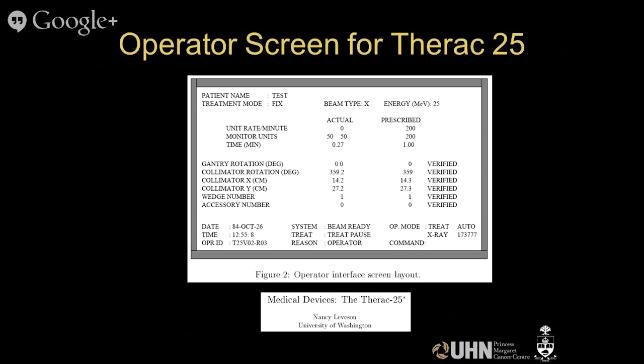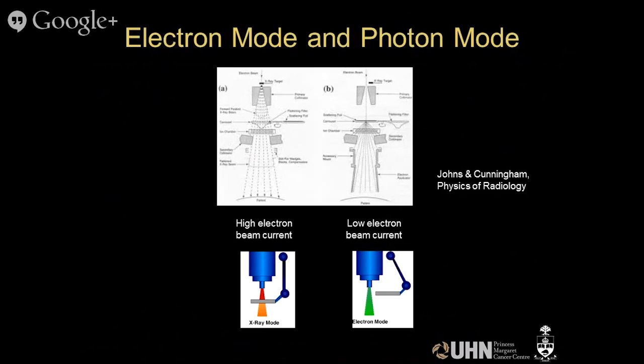So you can enter data into here. You can enter information about how the machine was set up. You can enter monitor unit information, and then the machine will accept that information, program it into the whole accelerator, and then deliver the radiation. So in theory, this was a good idea. But it turns out that there are some failure modes of these machines that can actually be rather dangerous if you're not looking out for them.